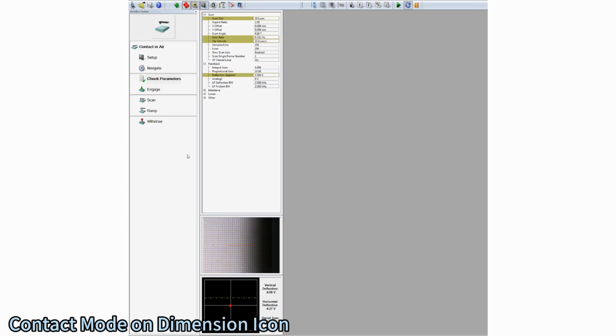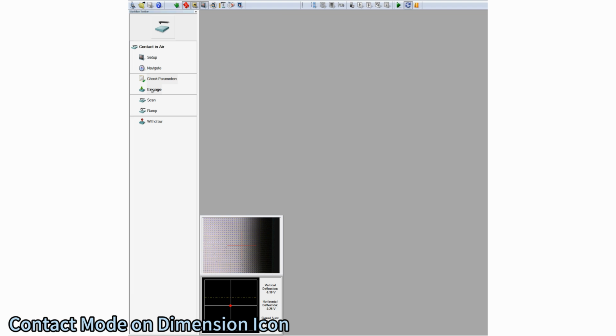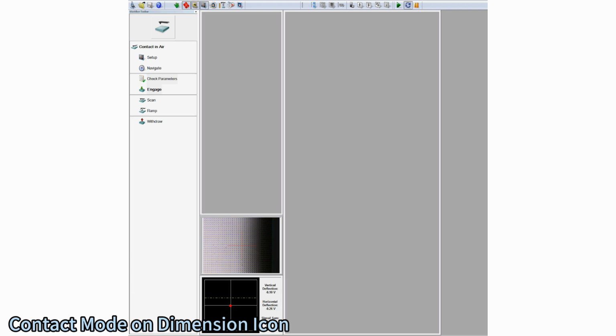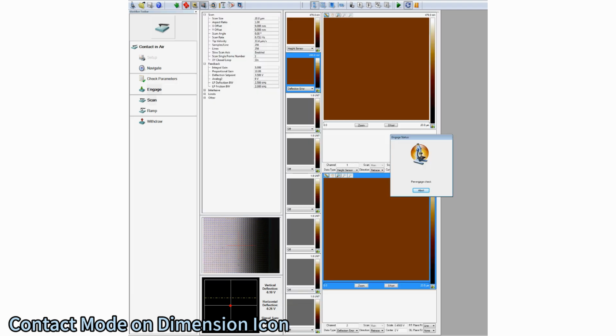Once the scan parameters are satisfactory, initiate the approach by clicking the Engage command. The approach process begins by shifting the focus to the probe and lowering the Z-stage motor until the probe encounters the force region above the sample. The Z-motor slows down and the piezo begins stretching downward until the probe deflection achieves the set point value. At this point, the Z-motor stops and the feedback loop takes over the control of the piezo and probe position while monitoring and maintaining the set point value.